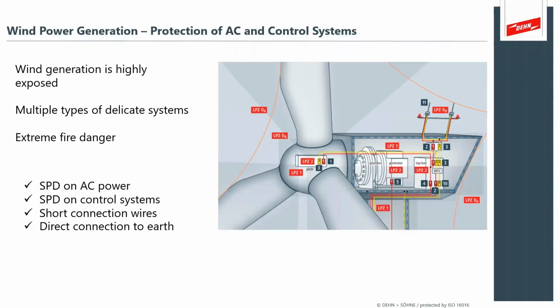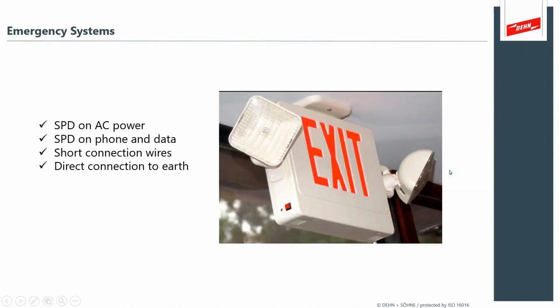We talked about requirements in the wind power industry, and we have a good combination of excellent wind energy applications here in the US and lots of lightning. And so this is a combination for the service industry that needs to go up and maintain these devices. There's any number of damage in the mechanical rotor systems that can be controlled with lightning protection and surge protection. So it's important in this industry, which has such high maintenance costs, tower climb, road access, and you know, of course, weather delays to go do any of this work. You can see that this is a really high importance to have addressed all of the applications within these inverters, where you're looking at all of the direct inverters and all of the IO controllers on these types of applications.